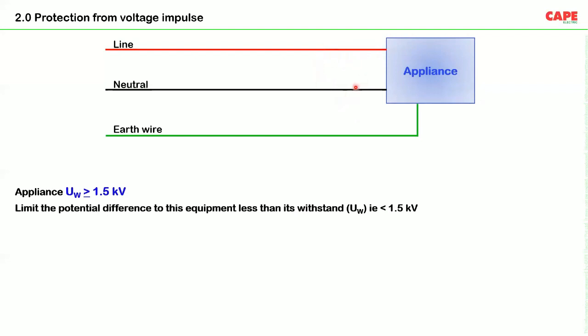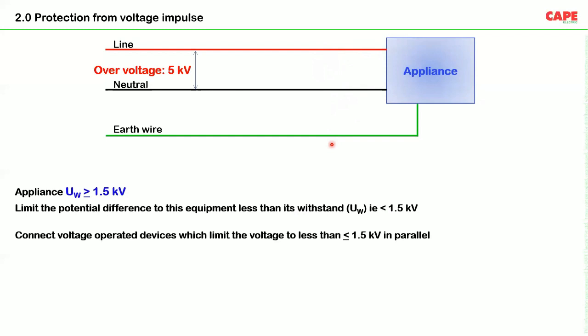So what do we do? We have to limit the voltage going into the appliance to less than 1.5 kV. Imagine in a typical condition, due to some reason, probably a capacitor switching or some operation, a voltage of 5 kV is coming between line and neutral. Of course, our equipment will fail under this condition. What do we do? We have devices called SPDs, which are connected in parallel, between line and neutral, for example, between neutral and earth, for example, between line and earth. In this particular case, I have shown 3 devices which are connected in parallel.